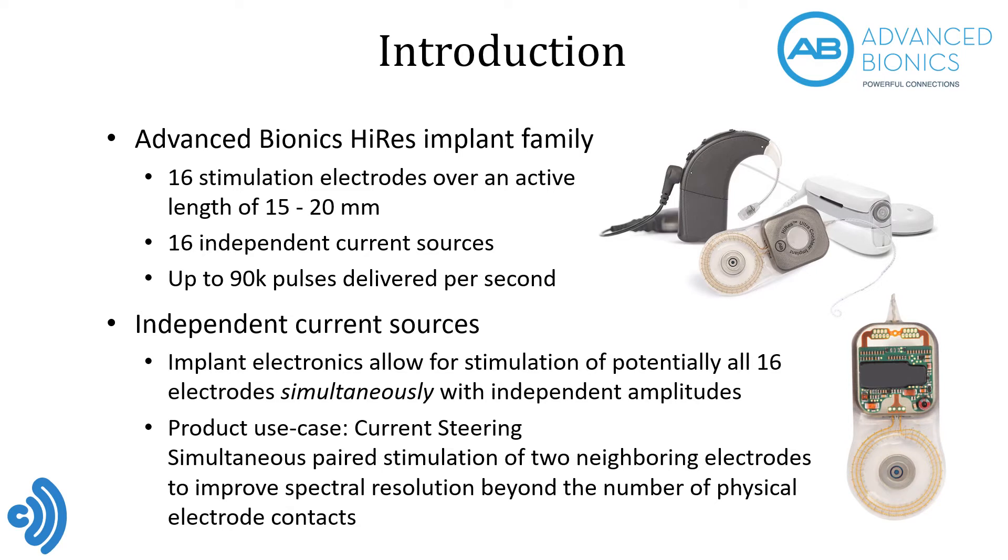You've heard about CIS, short for Continuous Interleaved Sampling, as a successful concept for CI sound coding that pretty much all modern strategies are derived from. In CIS, only one stimulating electrode is active at any one time. The HiRes implants of Advanced Bionics all have 16 stimulating contacts embedded in the silicon carrier. What sets our hardware and electronics apart is the fact that we also have 16 independent current sources, one for each electrode, which can stimulate the recipient at very high rates. So with our implant, we have the capability to stimulate any number of electrodes simultaneously with independently controlled amplitudes. And you can make use of this capability, if you like, in your own coding strategy.